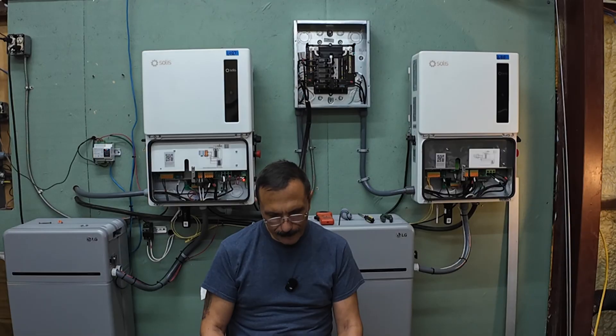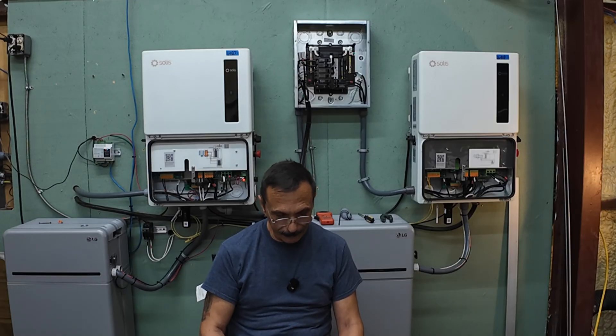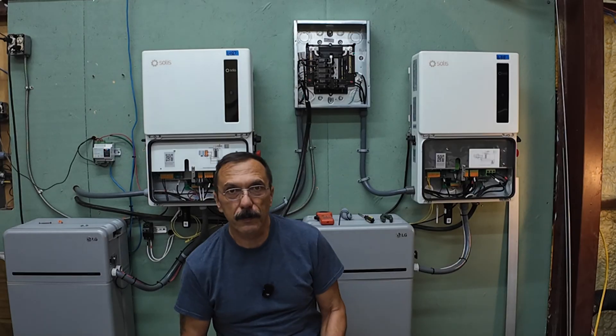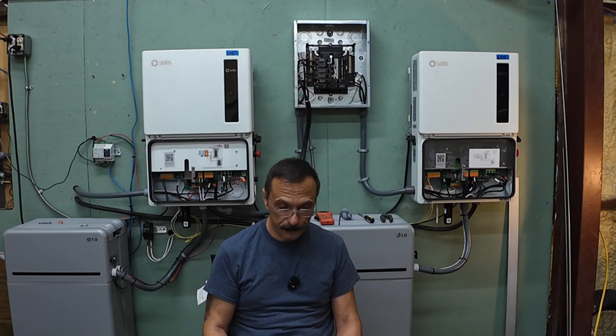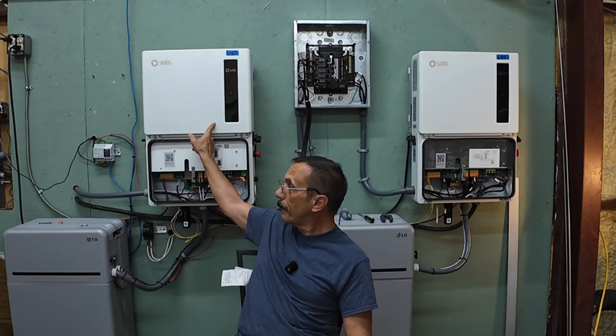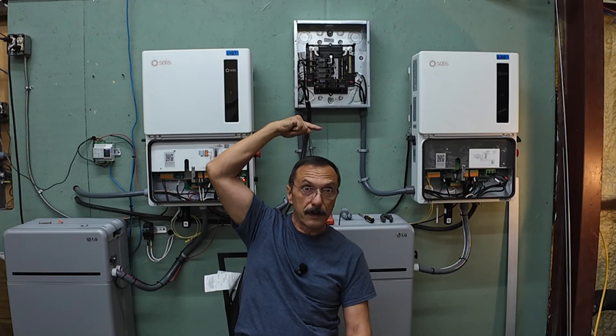All right, let's go over the settings. I've got my cheat sheet here so I don't miss anything. Solis S6 parallel sync settings: to set up the Solis S6 for parallel synchronization you must establish a master-slave communication network and configure specific settings for each inverter using the local Solis Cloud app. You're going to get your phone, connect to the Bluetooth on the unit, and get into the Solis Cloud app. The parallel sync setting ensures the master inverter's operational parameters are automatically applied to the slave inverters.